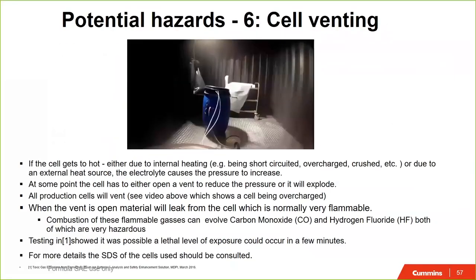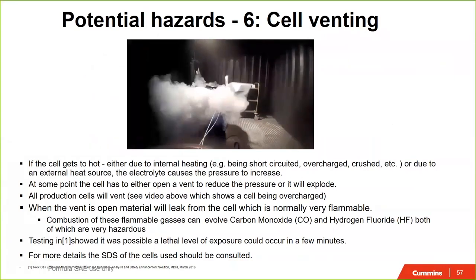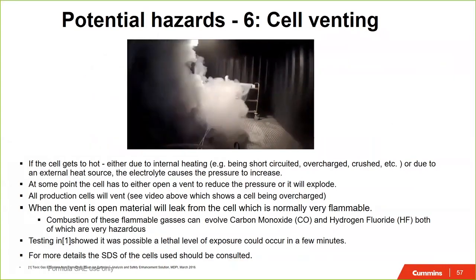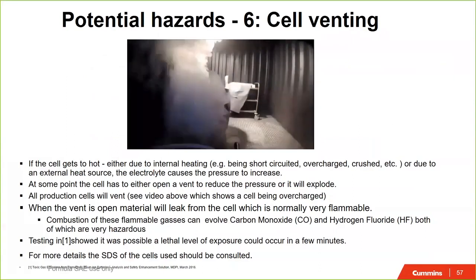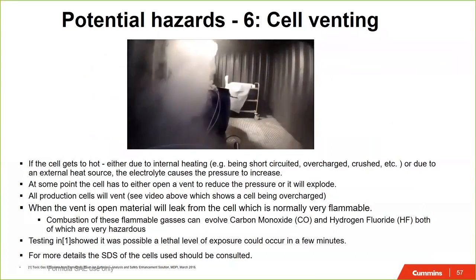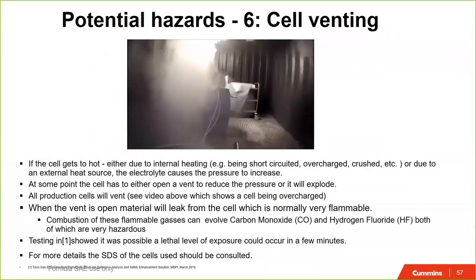Looking further at cell venting, what you're looking at here, this is an overcharge test. It's a single pouch cell inside a barrel, which is inside a 20-foot ISO container, standard shipping container. So this is to give you an idea of how quickly the smoke can generate in a failure, and that there are early signs. This one's a slow starter. So if you push a cell far enough, it will fail. And it will vent. The venting is the first stage.